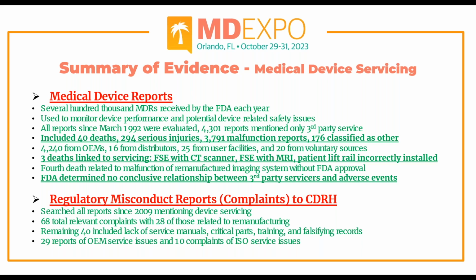So the FDA determined no conclusive relationship between third-party servicers and adverse events. What I want to make sure everybody understands is that the FDA did not come out and say there is no issue. What they said was there is no data, information, or factual evidence to support the allegation that there's an issue.